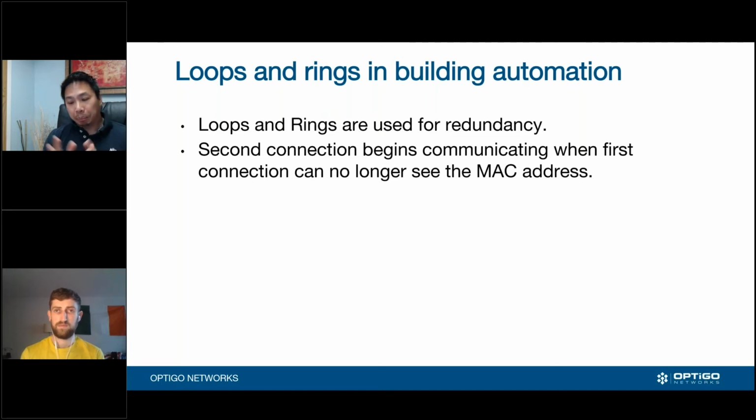One thing to keep in mind is that each of these VAVs, each of these controllers, no matter how small or how big, has a small address table in it. Okay, so let's say you take a controller and it has 2 ports. Internally, it will have a third port connected to the CPU of the controller. Inside that 3-port switch, it will have a MAC address. So when the ring is operational and it's steady state, all the traffic will go one direction. If you have, let's assume that you have a spanning tree protocol set up properly, everything will go, let's say for this example, to the left. Okay, so port on the left-hand side, and suddenly one device in the middle breaks.